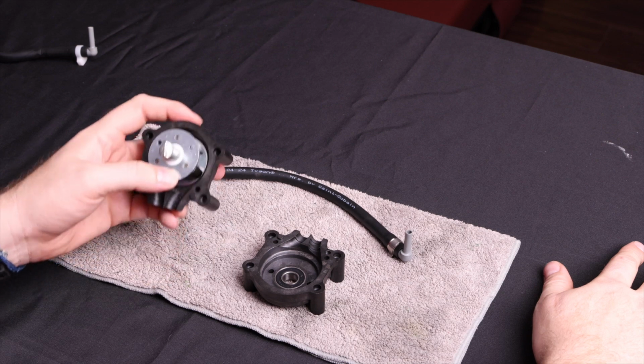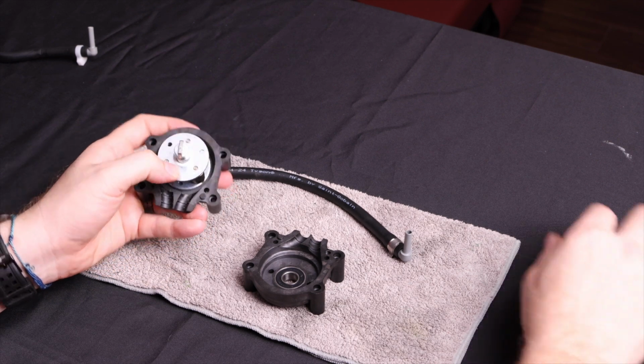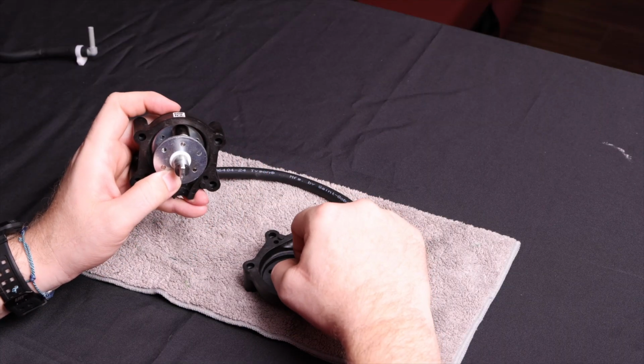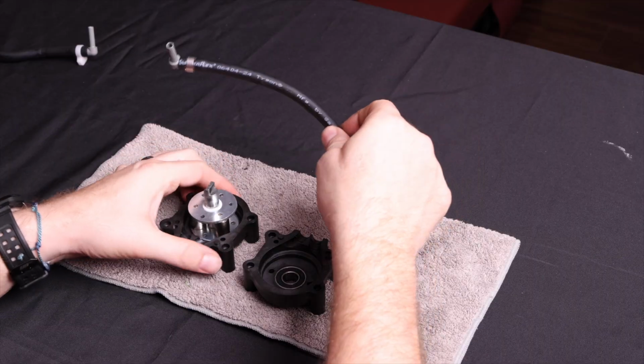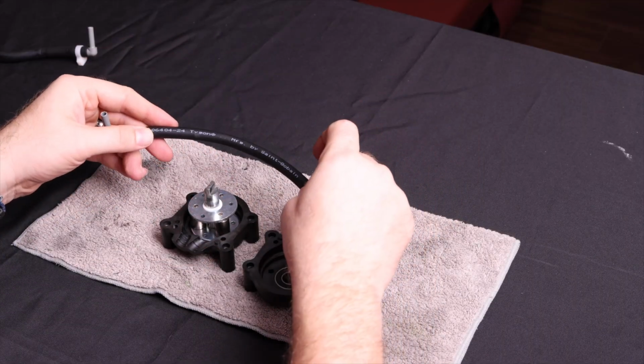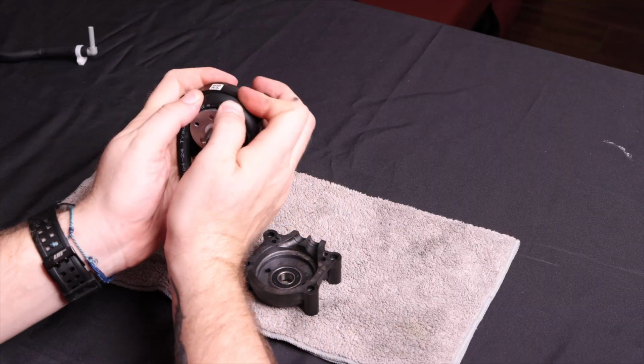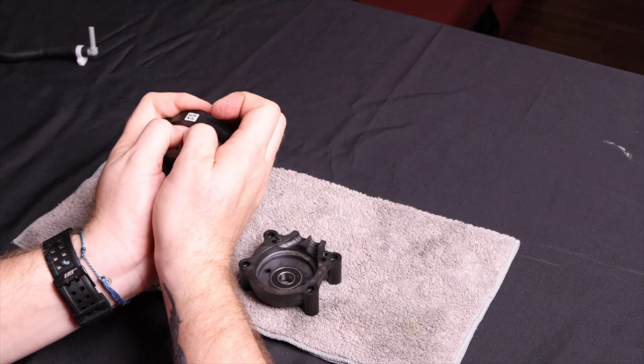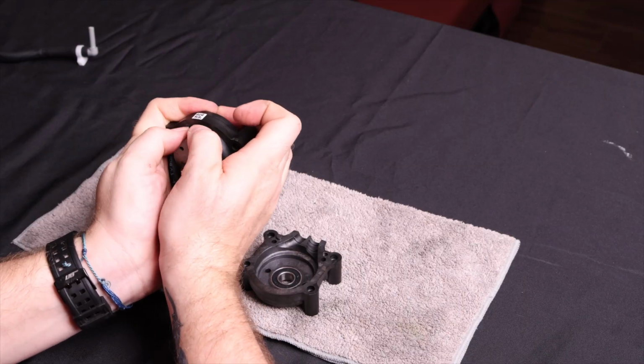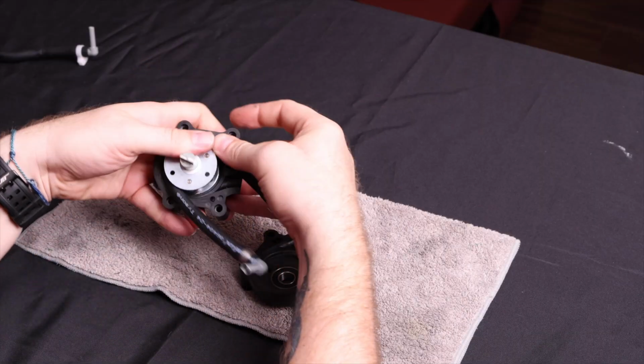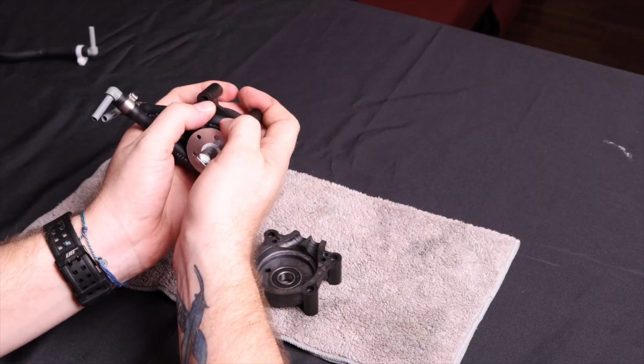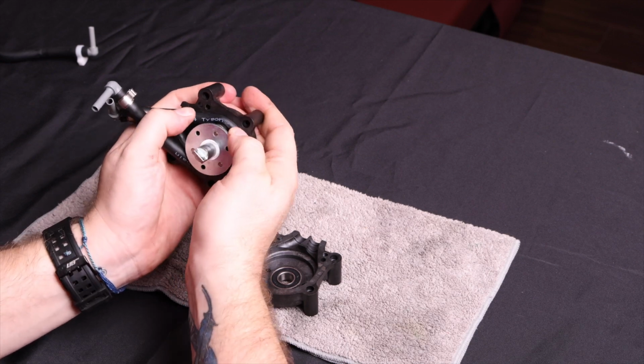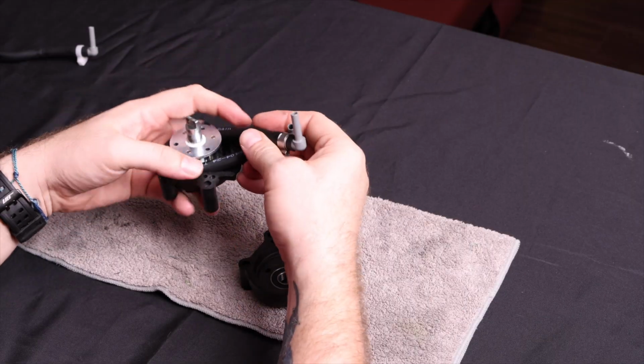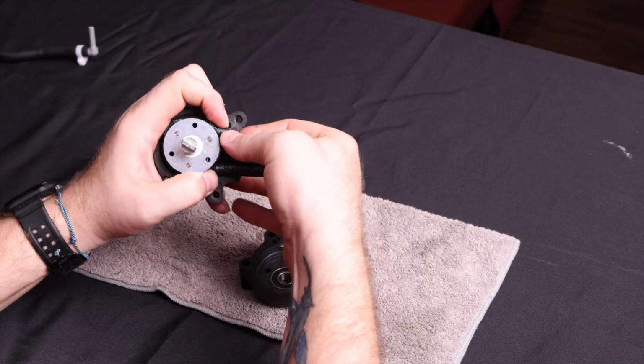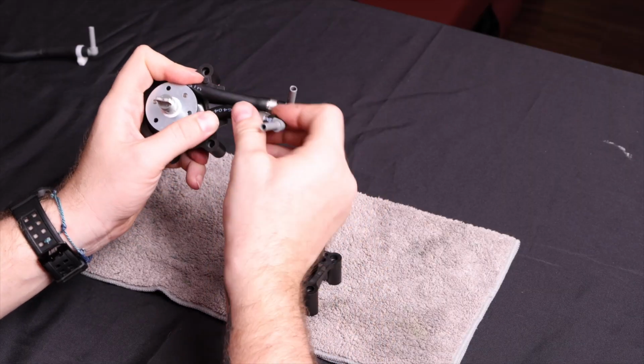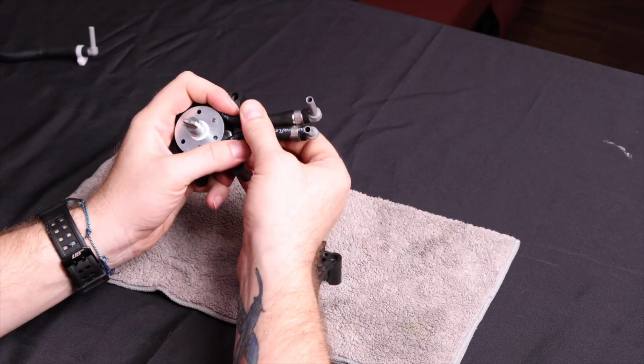If for some reason you do not have your key, you can still install the tube relatively easily. Take the top portion of the pump along with the bearing assembly. Line up one of the bearings at the top portion of the pump. Take your tube and with that top bearing, put the center of the tube into the bell. Using your thumbs, work the pump past the bearing and push in. Do the same around the rest of the assembly, gently pushing in. Once there, place the tube in the grooves and make sure they are even. If they are not, give them a gentle tug.